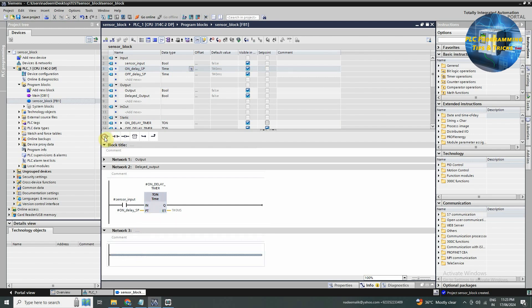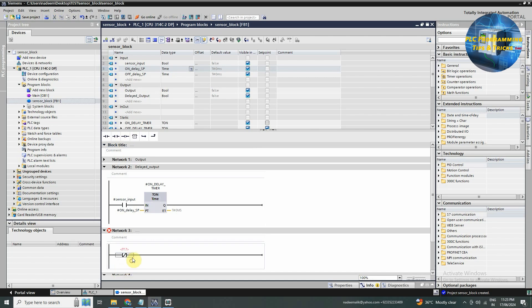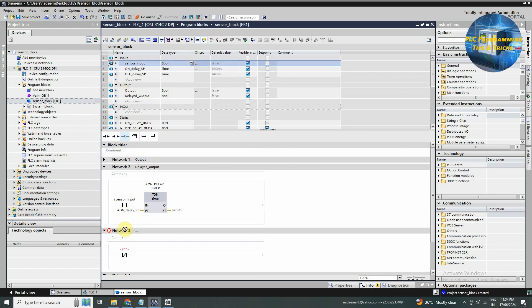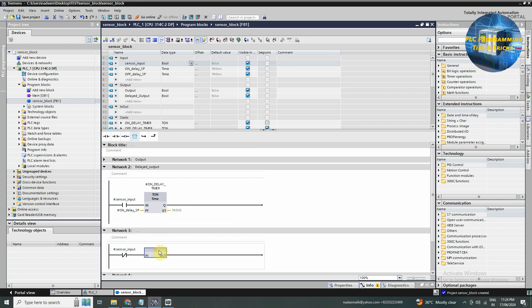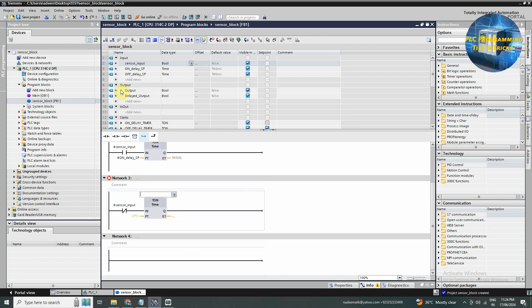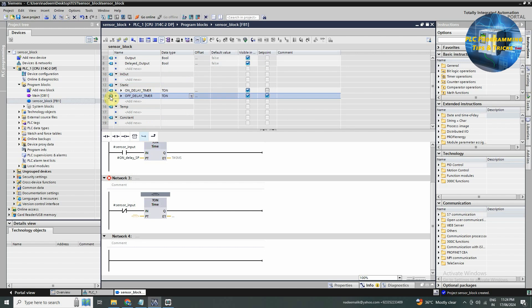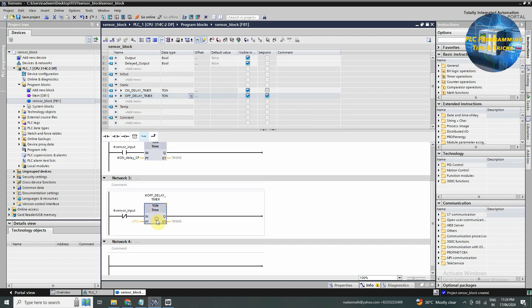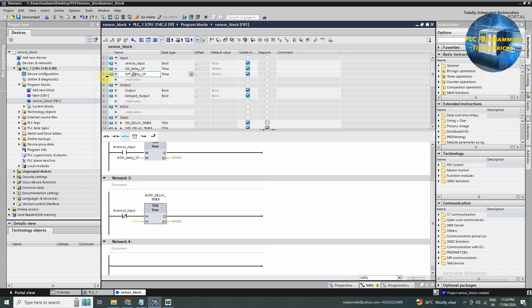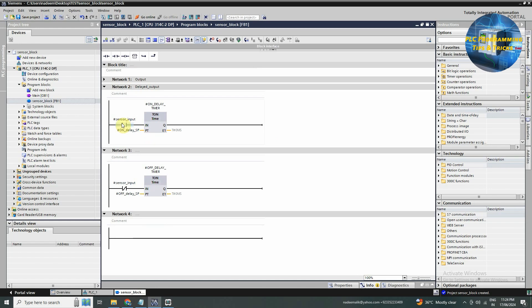In network number three, we will drag and drop a normal close contact and assign the sensor input tag. Next we will drag and drop a TON timer and assign the off delay timer tag to it. Now we will drag and drop off delay setpoint to the PT input of this TON timer. Now in network number two, as the sensor input turns on, it will start the on delay timer. And in network three, as the sensor input goes off, it will start the off delay timer.